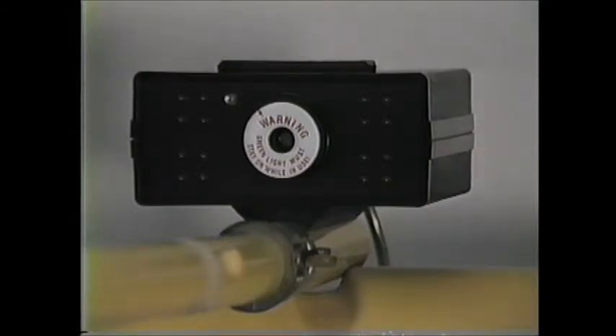When the unit is first switched on, all lights and the audio alarm should come on. This is a built-in test feature. One at a time, the lights will extinguish, starting first with the 11,000 volt bank, then the 7,000, 2,000, and finally the 600 volt bank.